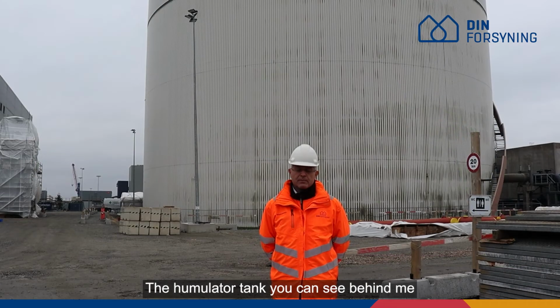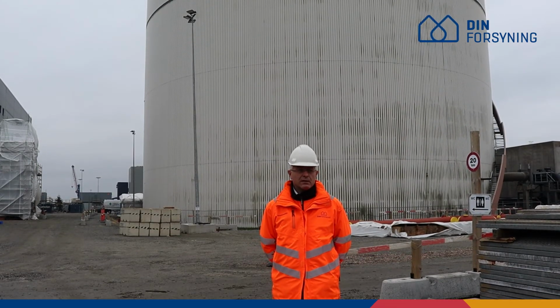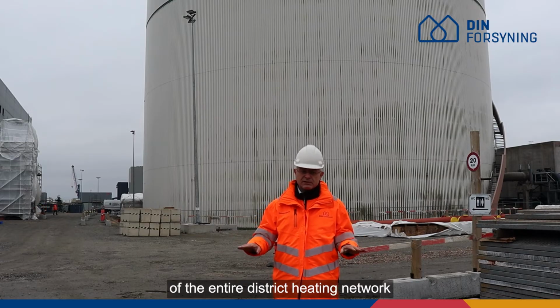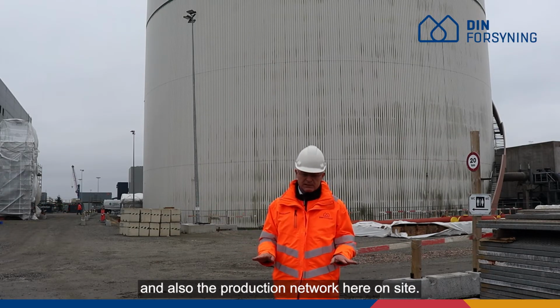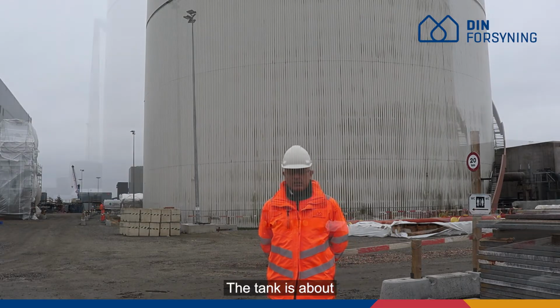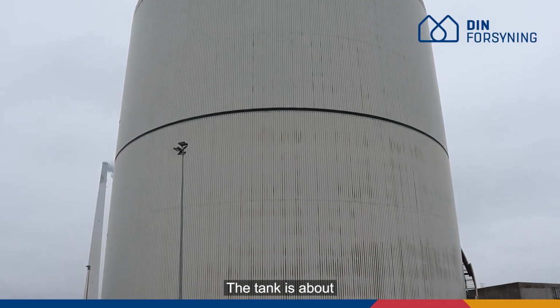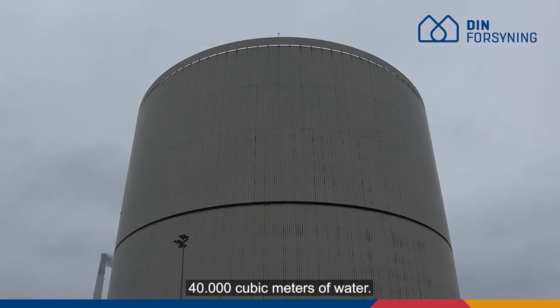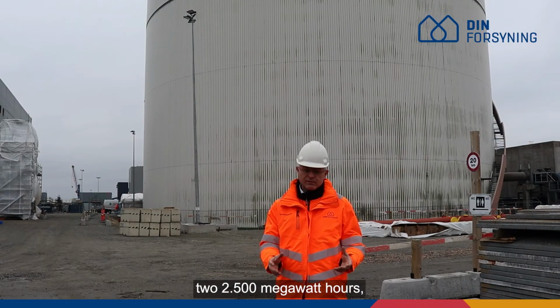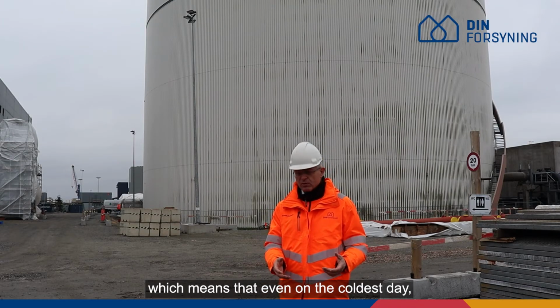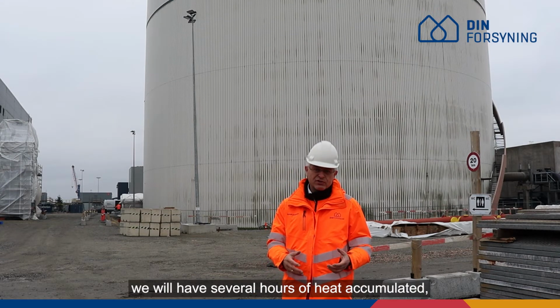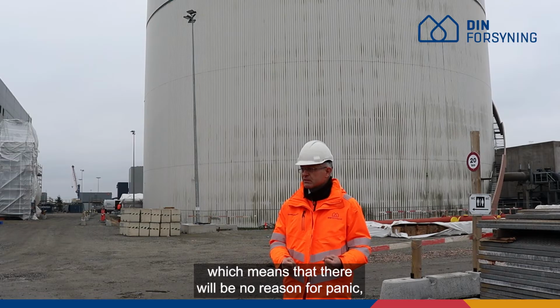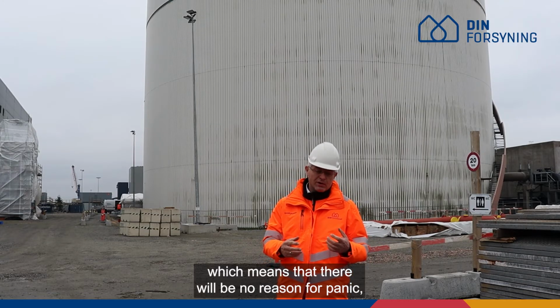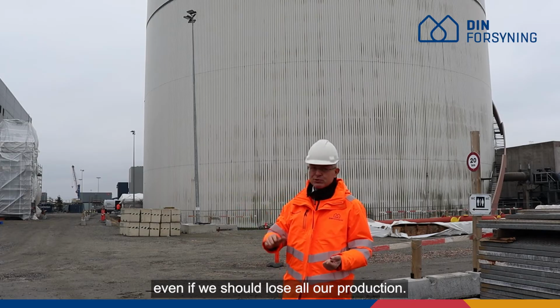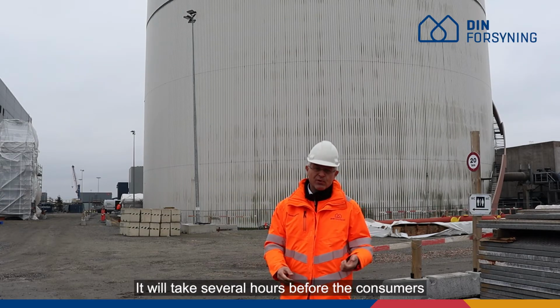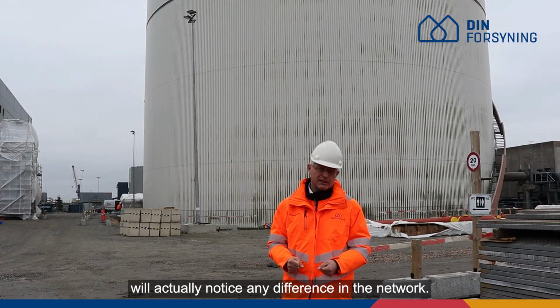The accumulator tank you can see behind me is 40 meters high. It provides the static pressure of the entire district heating network and also the production network here on site. The tank is about 40,000 cubic meters of water, corresponding to around 2,500 megawatt hours, which means that even on the coldest day, if the tank is full, we will have several hours of heat accumulated, which means that there will be no reason for panic. Even if we should lose all our production, it will take several hours before the consumers will actually notice any difference in the network.